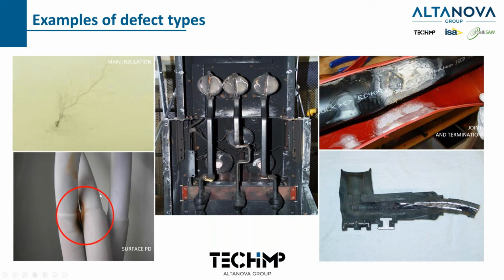And then at the bottom here, you see this burn mark. Obviously, this cable was installed incorrectly, and we have surface PD. It's called surface PD. You can see that. Here we have a switchgear that obviously has a lot of partial discharge going on.